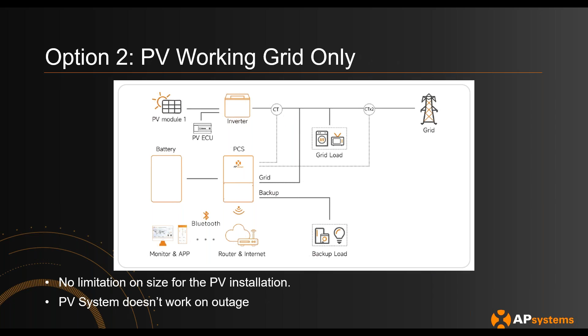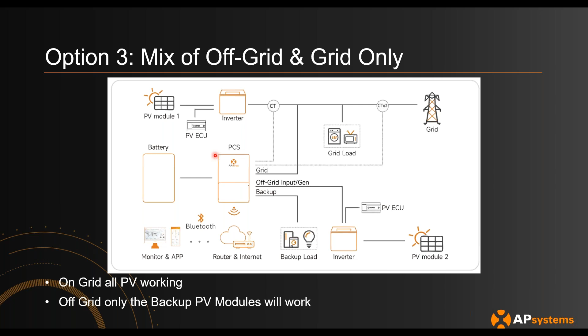A lot of customers often ask, say I have, for example, a 30 kilowatt AC system, what would you do? Because you can only put 14 kilowatts AC onto the PCS directly. So what you would do is split them out. You would have the PCS connected to half of the inverters on the off-grid port directly, and then you have the other half on the main panel. If you do it this way, you will have the entire array available when you are connected to the utility, but when you have a grid outage, you will just have half of the array available to charge the system, once again to prevent the PCS from overcharging its solar.